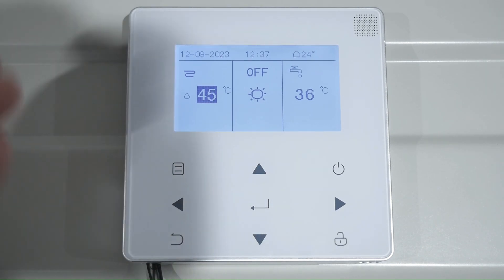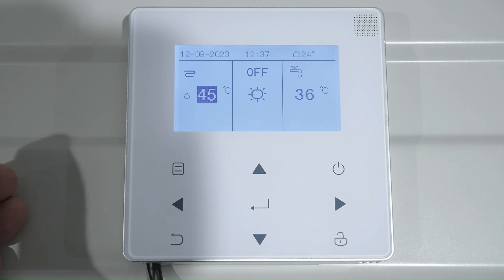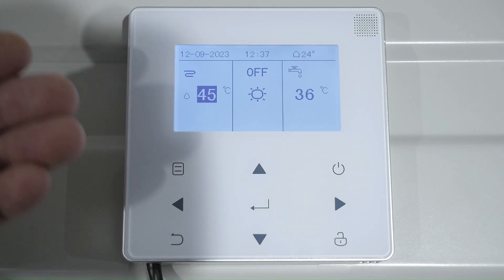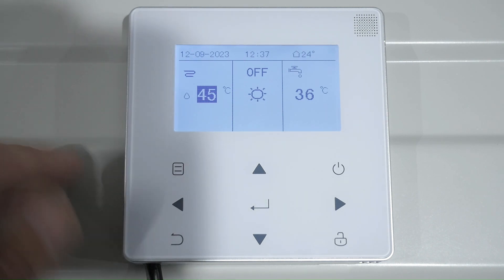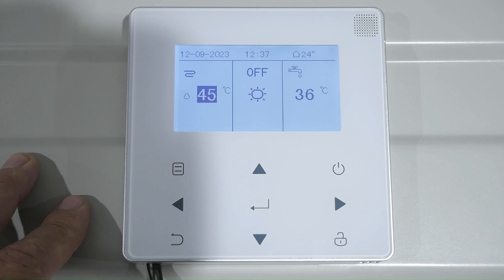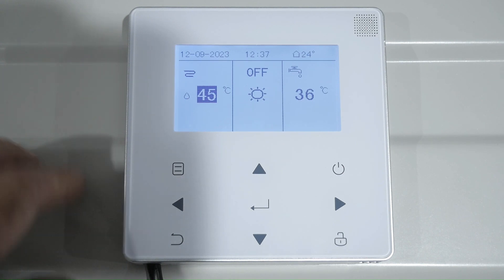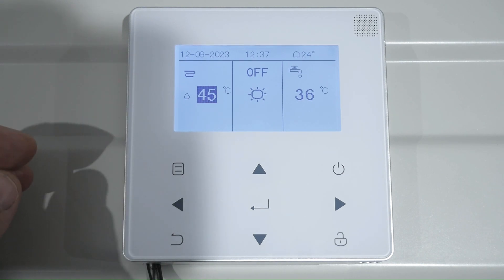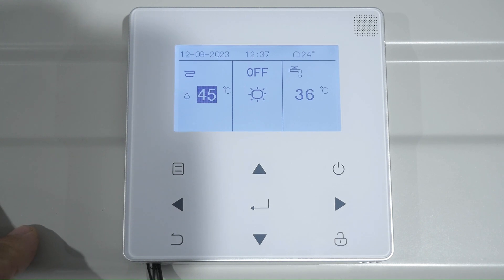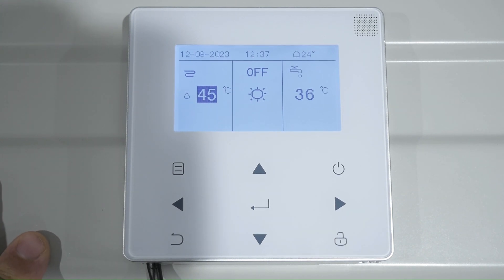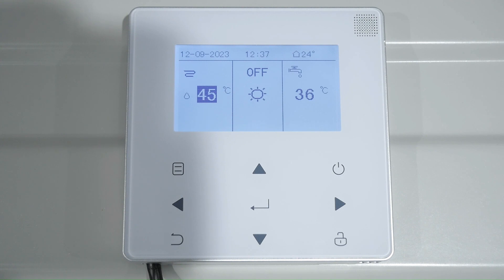You can just raise and lower the flow temperature, but we don't actually suggest you do that because this heat pump would have had a predetermined weather-dependent curve built into it which should meet the demands of your property. So what I'll do now is just show the heating come into demand by turning on a room thermostat over here.